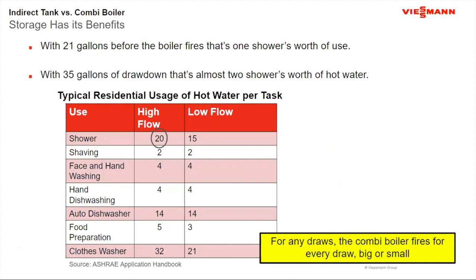In fact, if I look at that 35 gallon number, now I am pretty close to actually being able to get two full showers out of that tank's volume. So when I start to do a storage type water heater, one of the great features that it does is it utilizes the boiler to heat the hot water, but it doesn't cycle the boiler nearly as much as a combi does to keep up with the hot water demand.